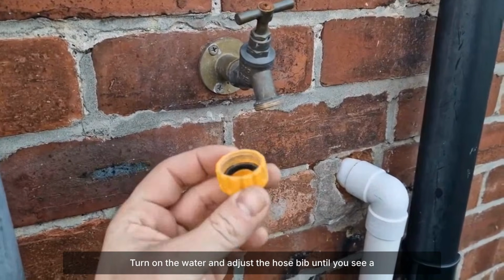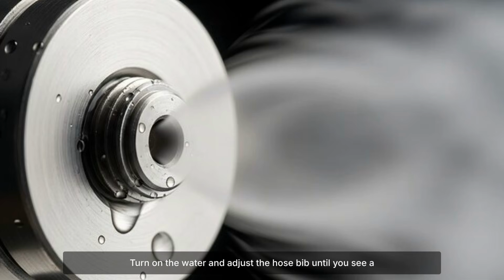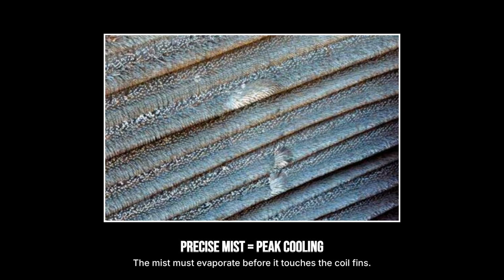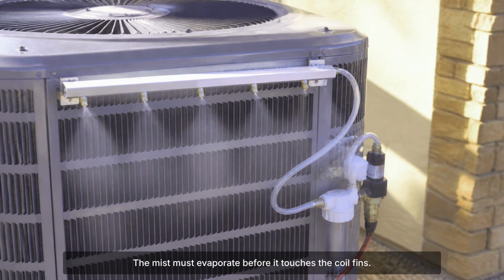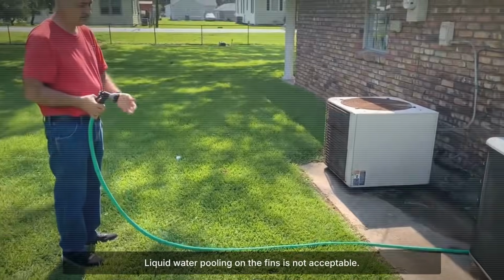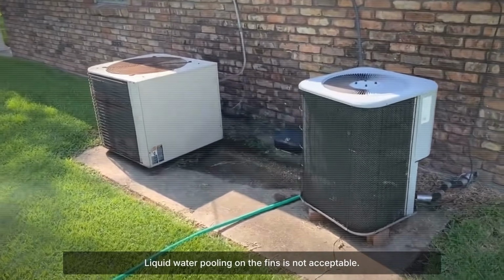Turn on the water and adjust the hose bib until you see a fine mist, not a stream, not dripping water. The mist must evaporate before it touches the coil fins. Flash evaporation in the airstream is the cooling mechanism. Liquid water pooling on the fins is not acceptable.